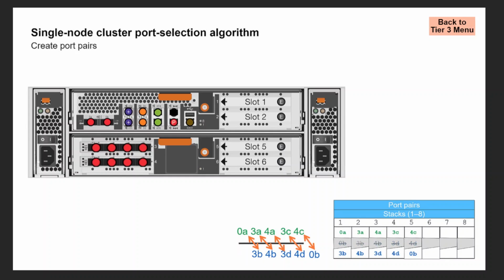If you shift the first entry in the row of B and D ports to the end of the row, and then shift all ports to the left by one column, the result is 5 sets of port pairs without any SPOFs. On the worksheet matrix, record the shift by writing the new port numbers in the bottom half of the boxes in the second row.